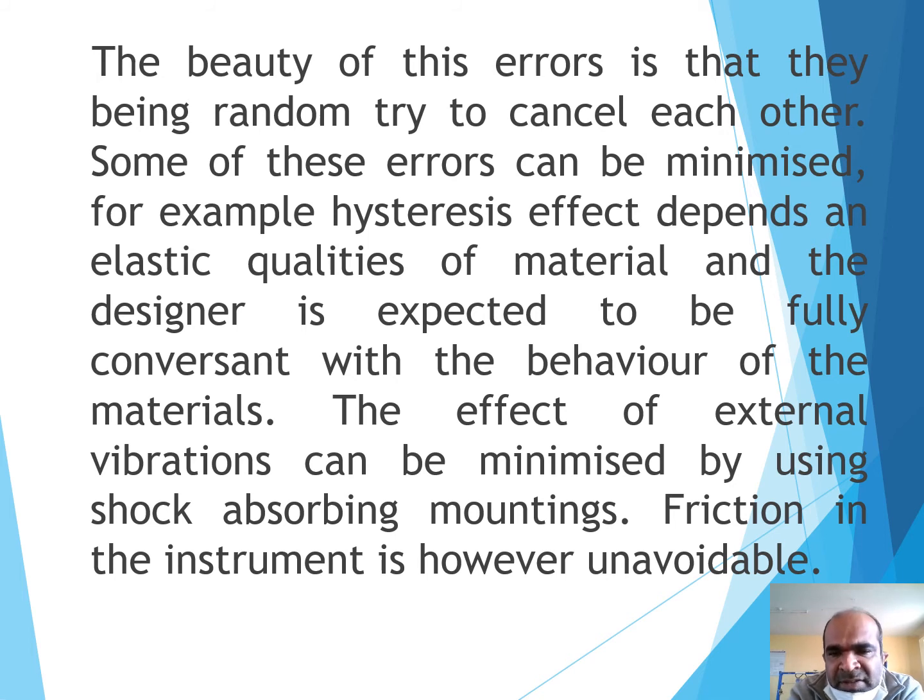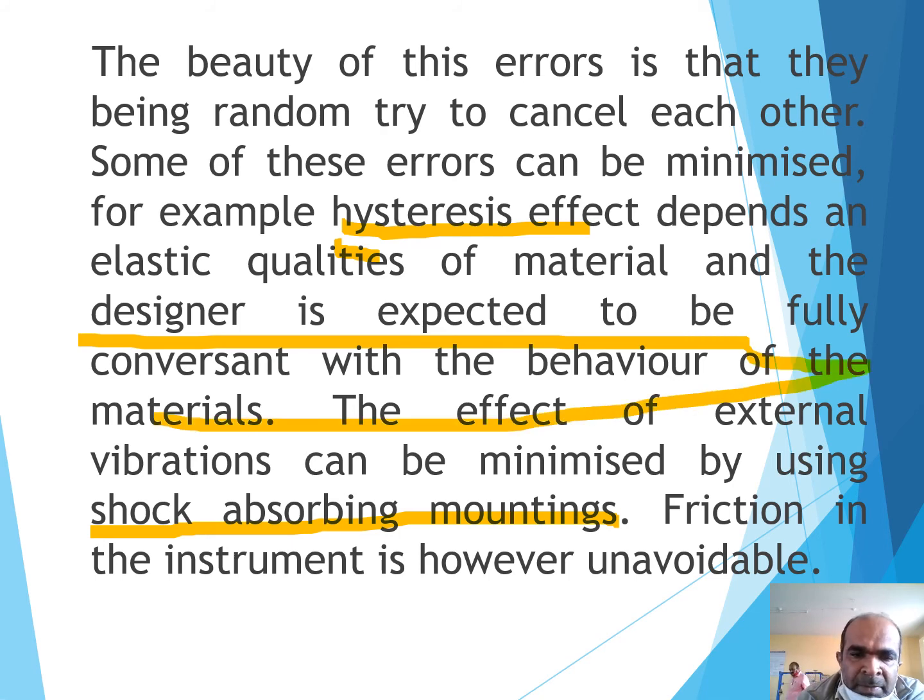For example, the hysteresis effect depends on the elastic quality of the material, and the designer is expected to be fully conversant with the behavior of the materials. The effect of external vibrations can be minimized by using shock absorbing mountings. Friction in the instrument is however unavoidable. You cannot avoid the friction, but you can use shock absorbing mountings to reduce vibrations. Similarly, if you want to reduce hysteresis, you need to understand the behavior of the material.